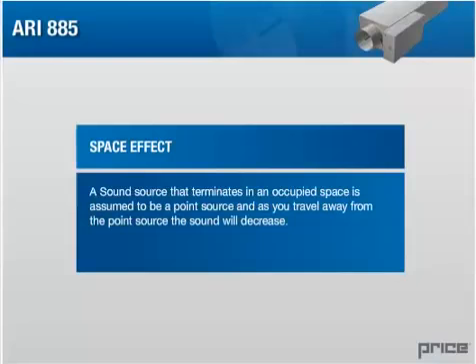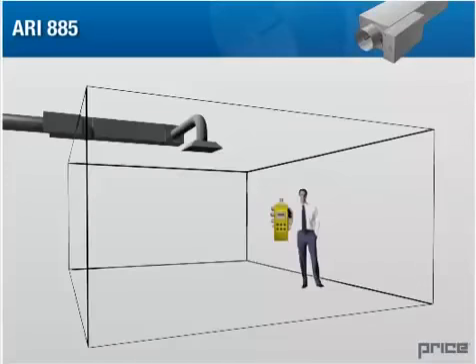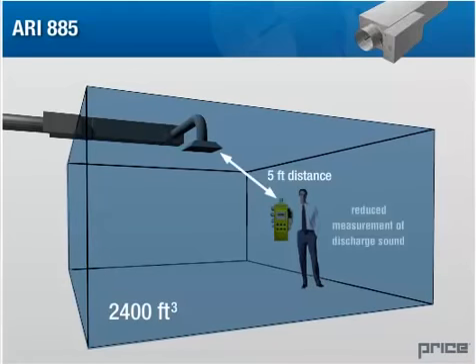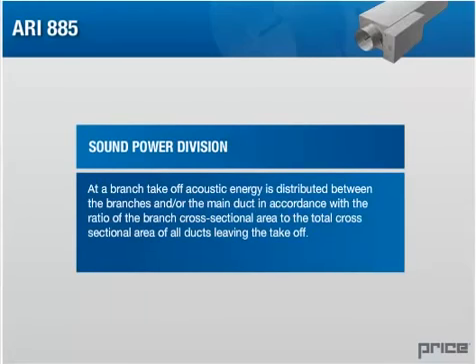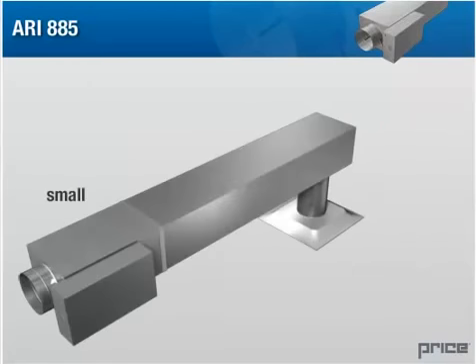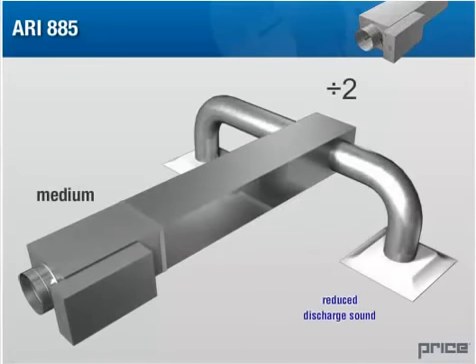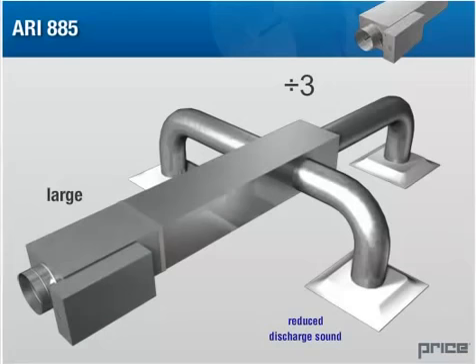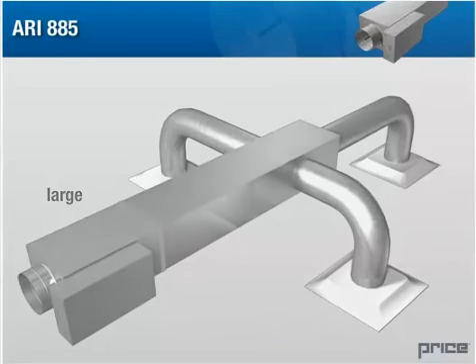Space effect. A sound source that terminates in an occupied space is assumed to be a point source, and as you travel away from the point source, the sound will decrease. The size of the room and the distance from the outlet will determine how we will perceive and measure the discharge sound. The standard assumes one outlet in a room with a volume of 2,400 cubic feet and a distance of 5 feet away. Sound power division. At a branch takeoff, acoustic energy is distributed between the branches and/or the main duct in accordance with the ratio of the branch cross-sectional area to the total cross-sectional area of all ducts leaving the takeoff. The standard allows for no branches for small units, 2 equally sized branches for medium units, and 3 equally sized branches for large units. The more branches there are, the lower the discharge sound will be at any single outlet.